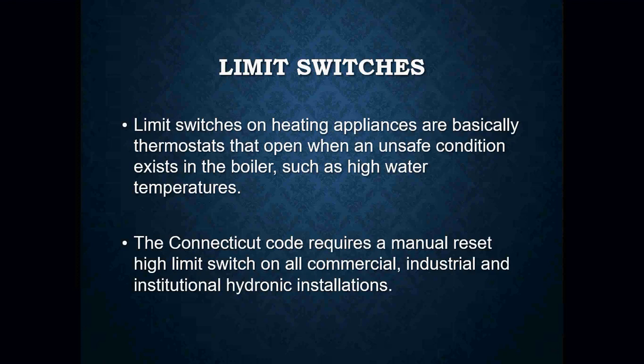Limit switches are the first thing we're going to cover. Limit switches on any of our heating appliances are basically thermostats — they are going to react based off of the temperature of that appliance and they are going to open when there is an unsafe condition. Since we are talking about hydronics, boilers, and steam heating, your limit switches are going to open and turn off the boiler when we have a high water temperature situation.